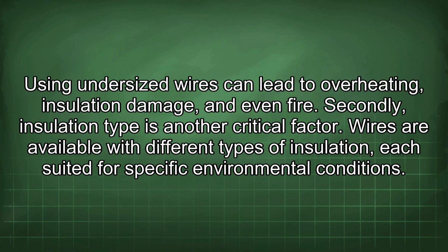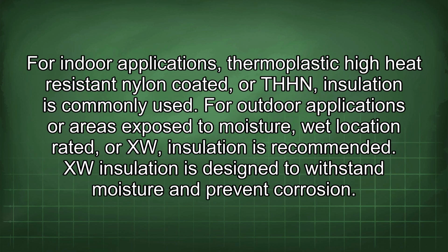Secondly, insulation type is another critical factor. Wires are available with different types of insulation, each suited for specific environmental conditions. For indoor applications, thermoplastic high heat resistant nylon coated, or THHN, insulation is commonly used. For outdoor applications or areas exposed to moisture, wet location rated, or XW, insulation is recommended. XW insulation is designed to withstand moisture and prevent corrosion.